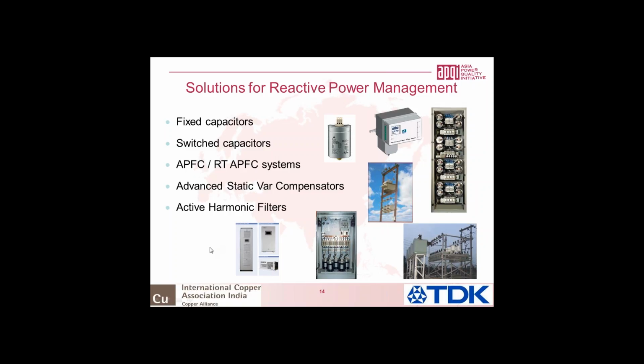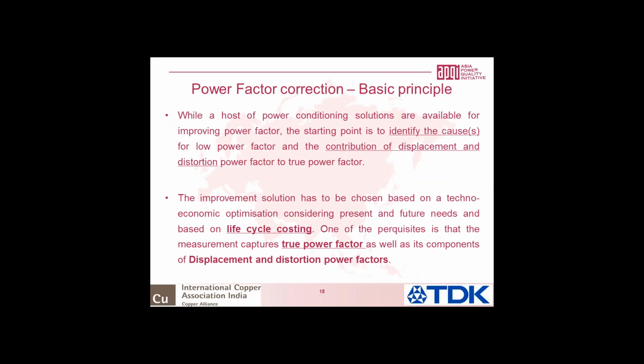Now let's look at how do we choose any of them for a given condition. For example, as I said, power factor correction, the basic principle should be based on identifying the cause for low power factor. You know, there are a lot of solutions available. Fixed capacitor, switched capacitor, IGBT based, thyristor based. It is not a dearth of solutions, but where we lack, in my opinion, is not in having solutions. There are too many of them, we tend to get confused and we don't choose the optimal solution. So in my opinion, the starting point is to identify the cause of low power factor. What is causing the low power factor? Is it because of reduction in displacement power factor or reduction in distortion power factor? After we have identified the cause, then we can choose the right solution.